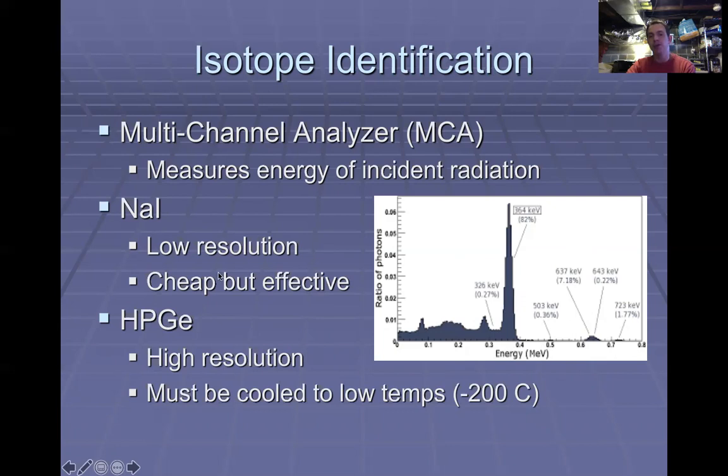The problem with them is that the only way they work is in incredibly low temperatures. So you need to have one of these detectors essentially immersed in liquid nitrogen. That's how they are used. A lot of them, if they come up to room temperature, the crystal will be irreversibly destroyed. So it's a big deal to keep these instruments maintained, keep a stock of liquid nitrogen for them. But in terms of their ability to ID isotopes, they're irreplaceable. You need to have one of these if you're working in some sort of QA lab where you have to make sure there's not contaminants and such.